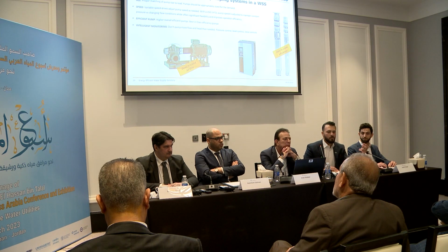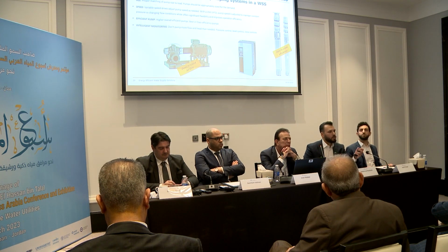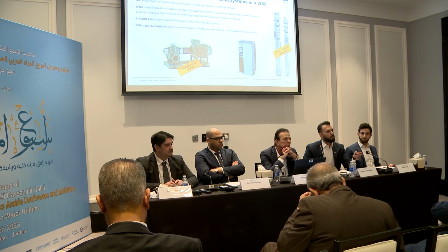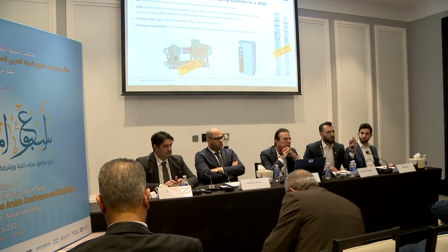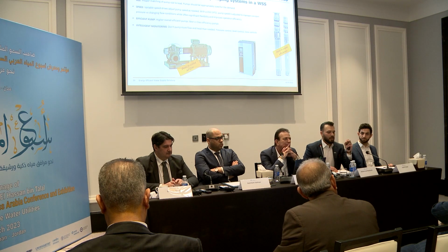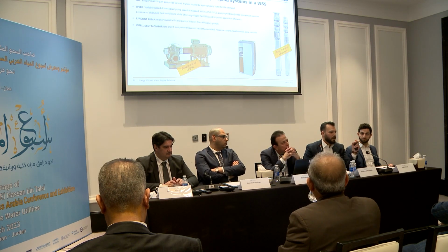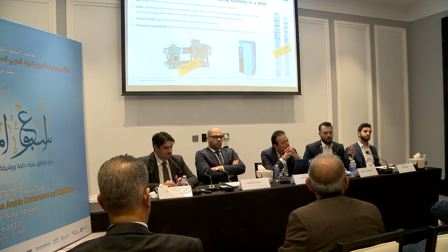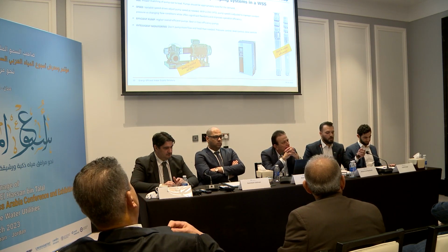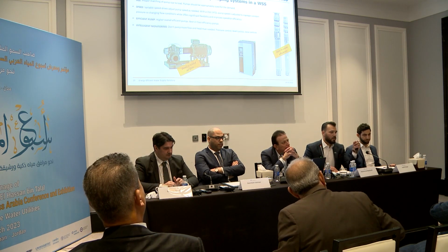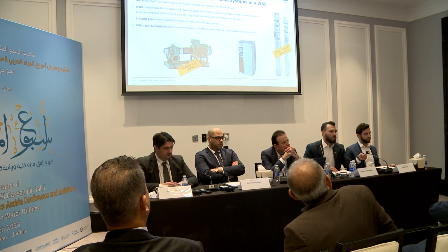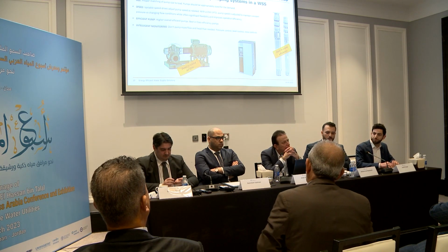So usually there is a way to save more energy by pumping with less pressure, not maintaining the pressure, because at less flow you need less pressure to deliver. So this is a way to do it, and of course you also need very high efficiency on the hydraulic side and also on the electrical motor side to reduce the energy consumption.